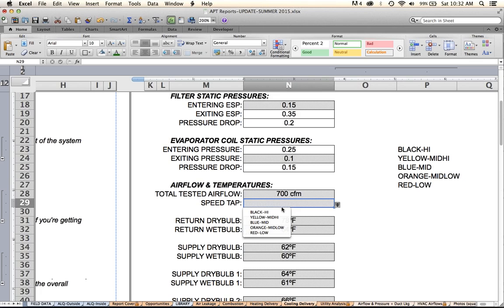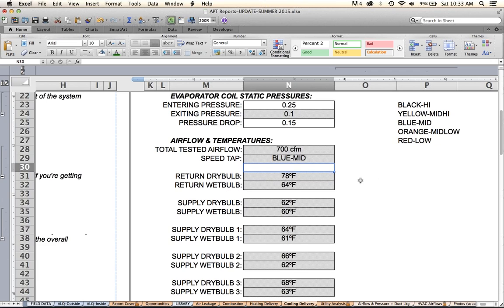Okay. The speed tap, and this is something that I actually just learned about, and I've been doing this for 7 years. There are 5 wires in these furnaces that I have been commissioning, and black, yellow, blue, orange, and red is the order of the speeds. These are wires coming from the fan, and you plug them into the circuit board so that when cool activates on the circuit board, it sends electricity to this little nubbin that's pointing out, and you attach the black, the yellow, the blue, the orange, or the red to that little nubbin, and bam, you've got whatever speed that fan is programmed to work on from that wire. So in this case, let's just say that I'm on blue. Okay, now there's all kinds of different things that we could go into here. This is not an HVAC class that I'm trying to give. So if you have a ton of questions at this point, just hang tight.